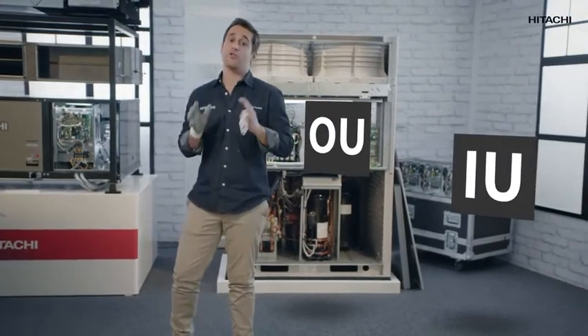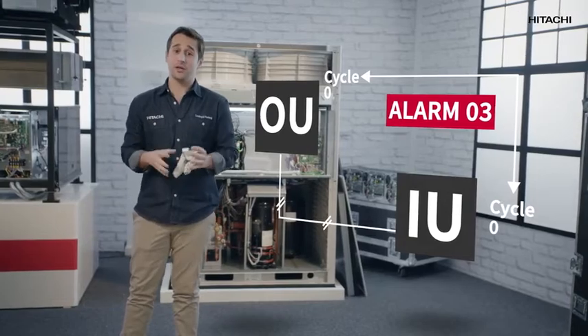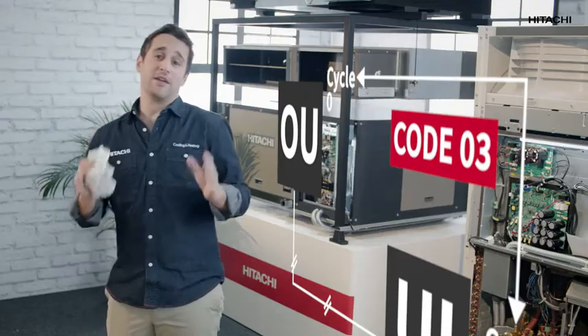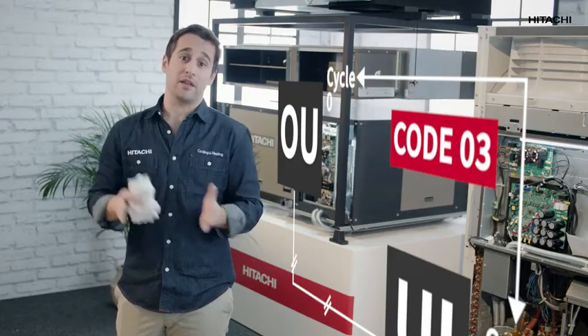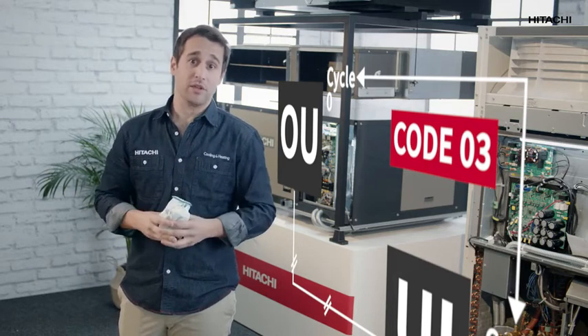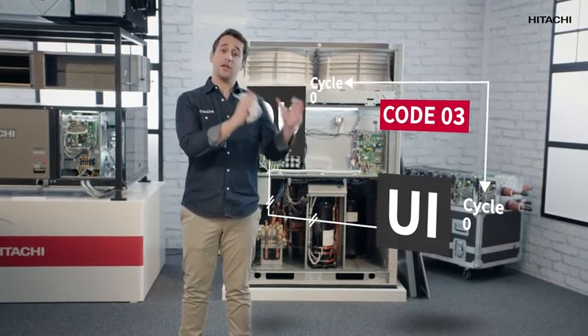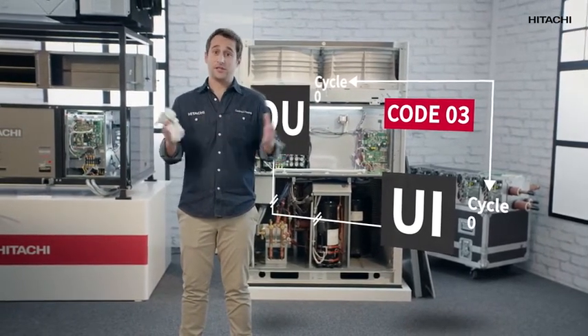Another possible reason for triggering the 03 alarm could be a communication setting fault between the indoor unit and the outdoor unit. If the cycle of the indoor unit and the outdoor unit does not match, we have a communication problem which triggers the 03 code. In order to deactivate the 03 code, the cycle of the indoor unit and the outdoor unit has to be the same.